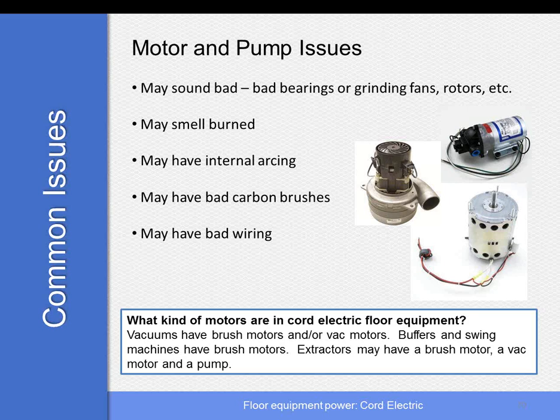On to the motors and pumps. Some issues with a bad motor or pump: usually it's the sound. Sound's the first thing that'll let you know. You can hear a grinding sound, a rubbing sound. The pitch may get higher or lower, but if you use the machine daily, you'll notice when the machine's sound changes. And bad bearings go bad.